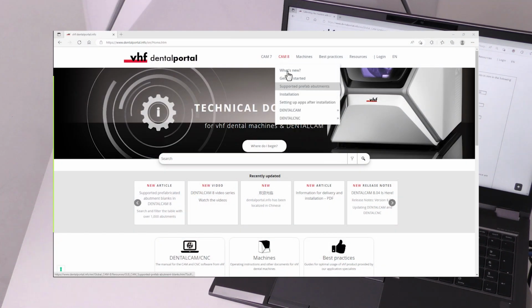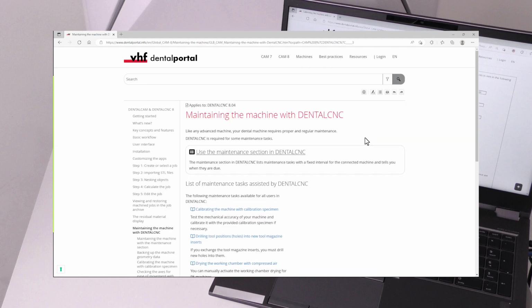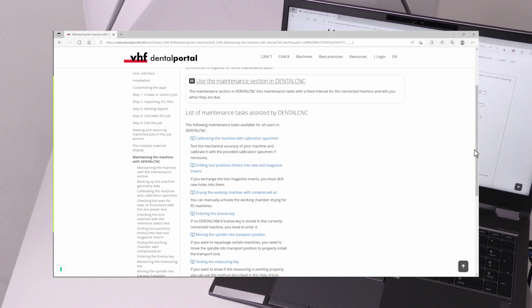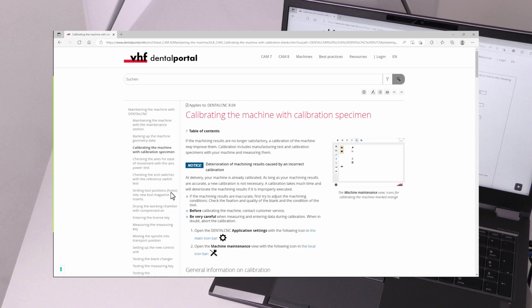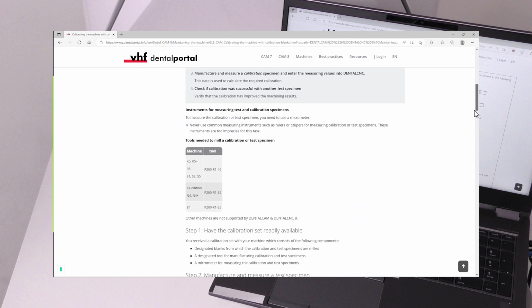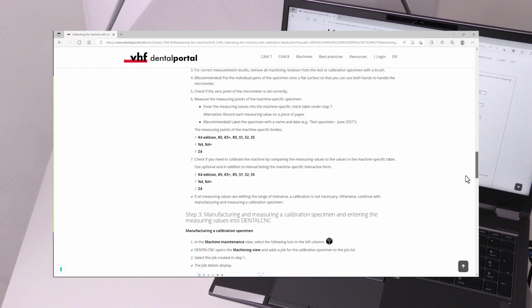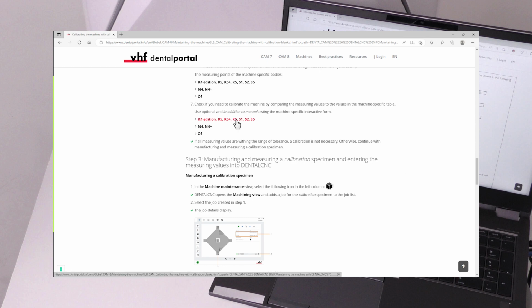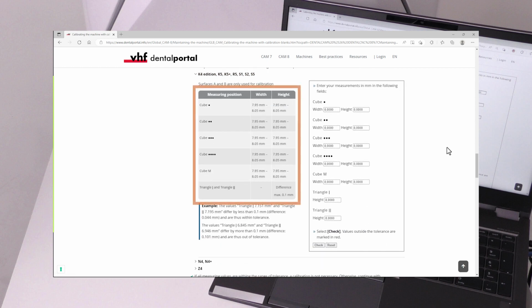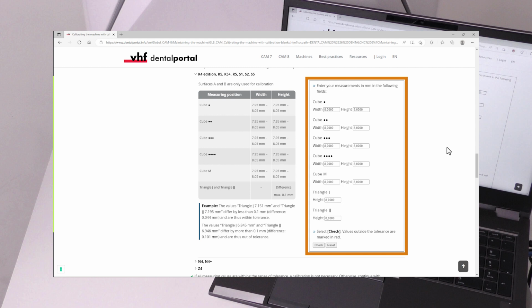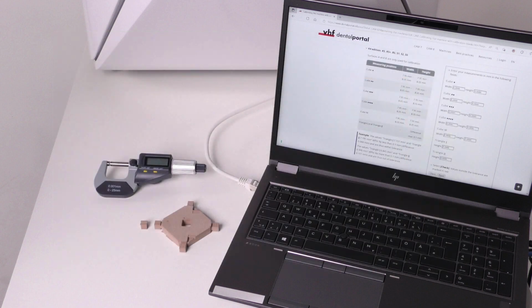Open the help article on calibration at dentalportal.info as shown, or select the link to the help article in the video description below. Scroll down to step 2.7 and open the machine-specific drop-down section. The section contains a table which lists the tolerance ranges for a manual check on the left, and a check table for an automatic check on the right. For this, you need to enter your measured values into the check table. Alternatively, you can record your measured values on a piece of paper and manually compare them with the machine-specific tolerances.